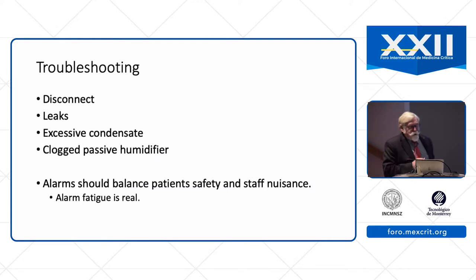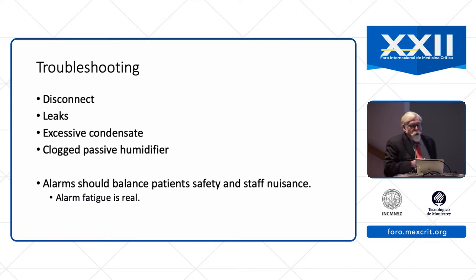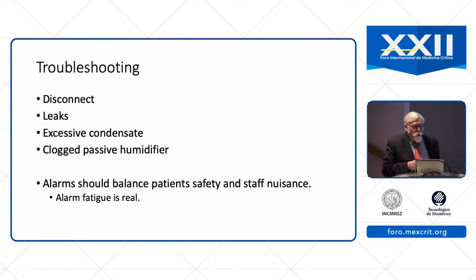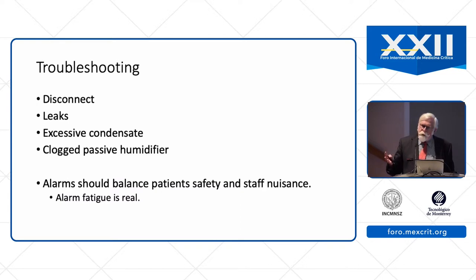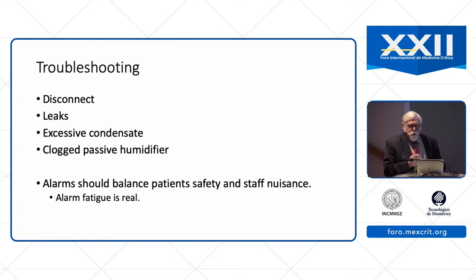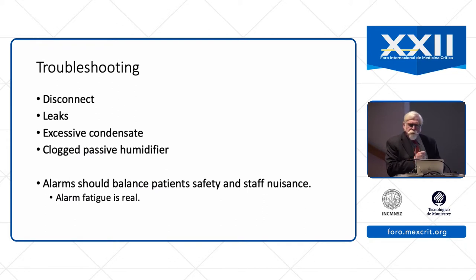A few things about troubleshooting. It's important that we pay attention to the technical aspects of the ventilator circuit. We want to avoid issues such as disconnection of the ventilator circuit from the airway. We want to monitor for leaks in the system. If the exhaled tidal volume is much lower than the inhaled tidal volume, there's a leak — which might be among the connections in the circuit, around the heated humidifier and its connections, or because the cuff is not fully inflated on the endotracheal tube.